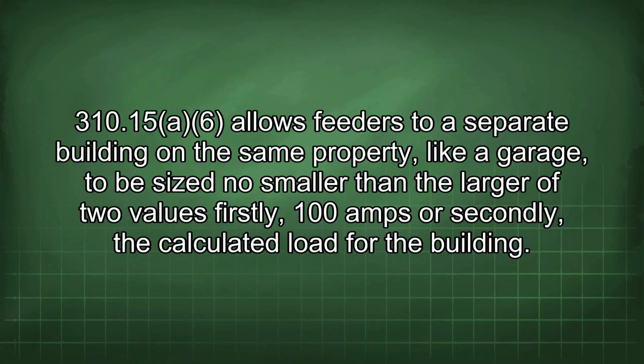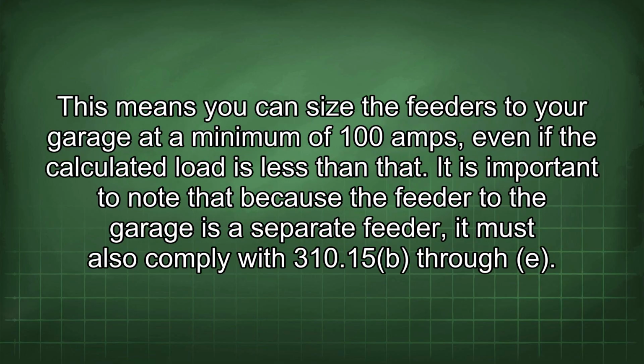310.15 allows feeders to a separate building on the same property, like a garage, to be sized no smaller than the larger of two values: firstly, 100 amps, or secondly, the calculated load for the building. This means you can size the feeders to your garage at a minimum of 100 amps, even if the calculated load is less than that.